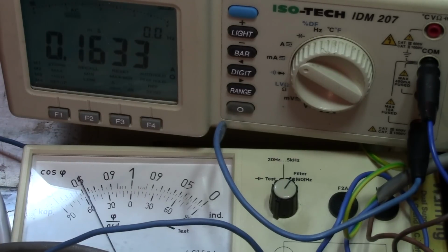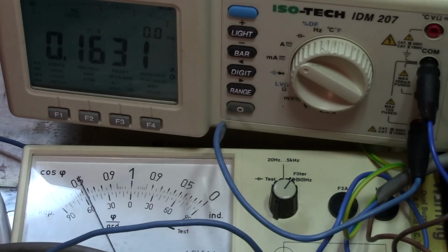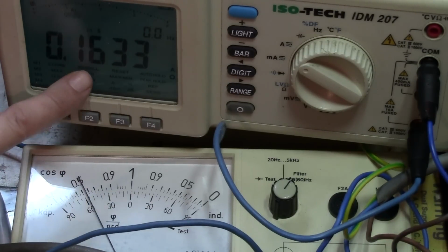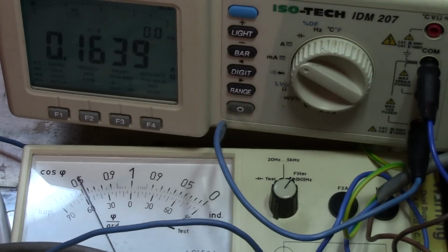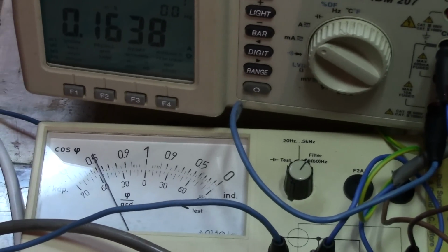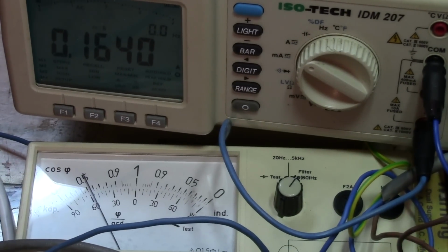Loved it. Right, so now you can see we're almost back to where we were before, 0.5, and we're getting up higher in the milliamps again, so we're up to 163. So you can see how it all affects. Basically, we're aiming to get that needle at 1, which is unity, and when you get it at unity, it will pull less current, and that is why we use power factor correction. So I hope that explains it a bit more for you guys. Sorry about the dodgy camera angles going on there. Nothing I can really do about that.